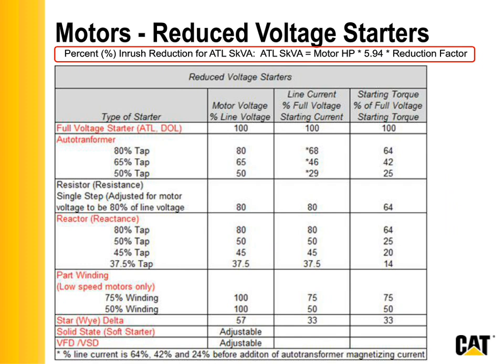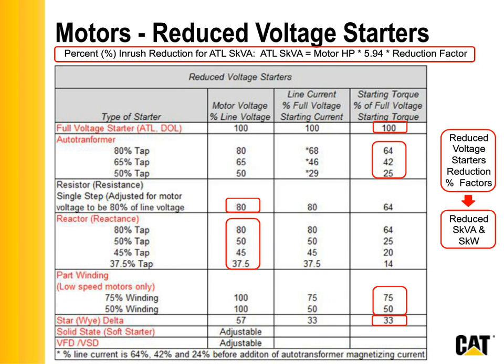And so here I have provided you a table that you can reference later on. In this table, one of the things that sizes a three-phase motor is DOL SKVA, direct on line or across the line SKVA. That's one of the things that is used to size your motor, to size your genset. And up there at the top, I show you the equation to calculate your DOL SKVA. Now, if you are able to utilize a reduced voltage starter, you can reduce your sized genset sometimes significantly.